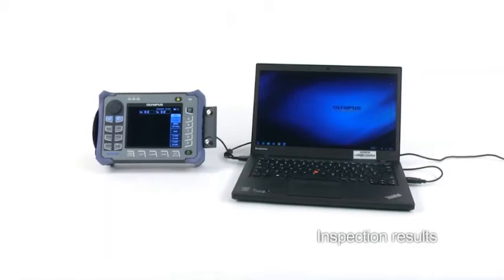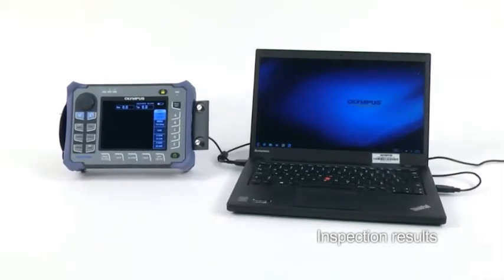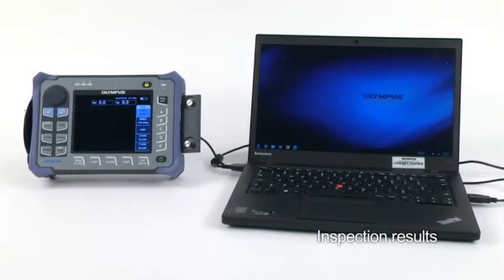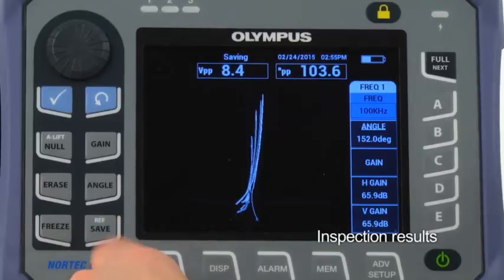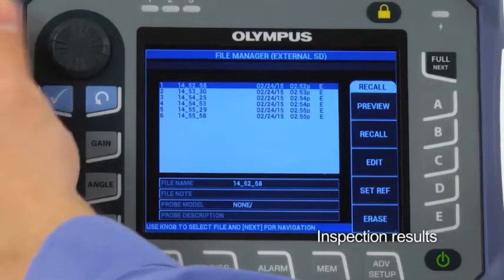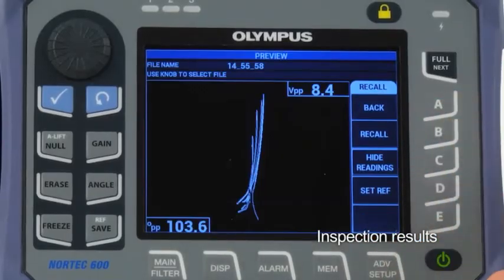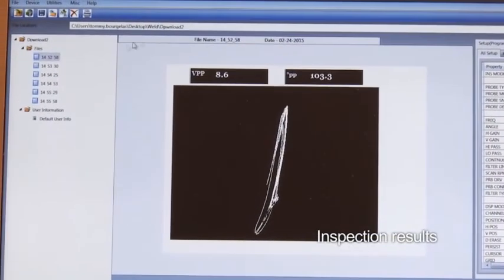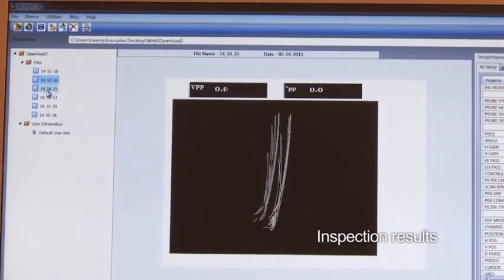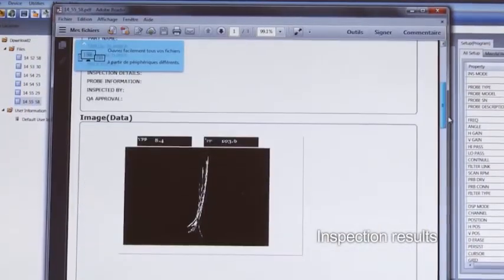Unlike MPI, recording inspection results is efficient with the Nortec 600 weld inspection solution. Files can be saved at any time during an inspection, then previewed on the instrument or downloaded to a computer, where a full report can be easily produced in the Nortec PC software.